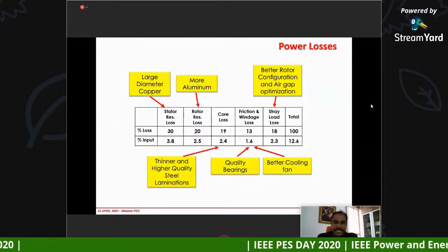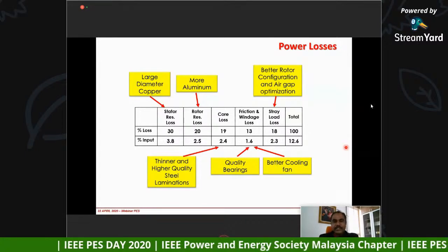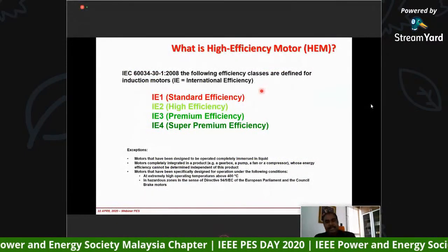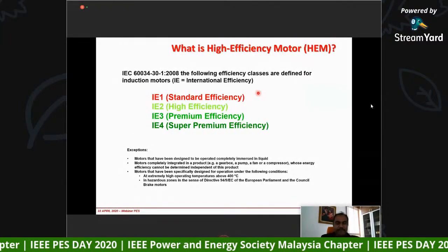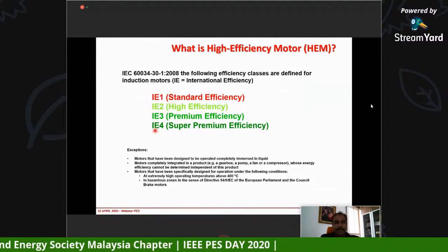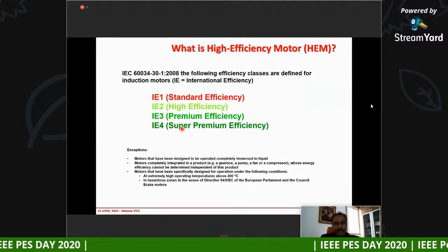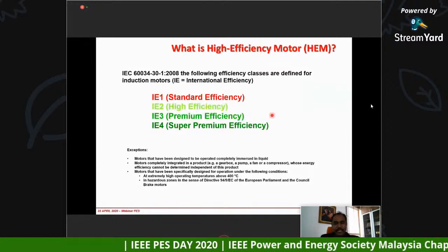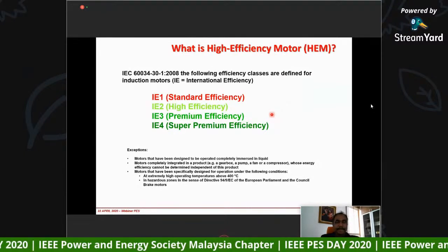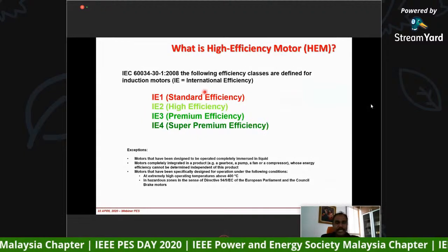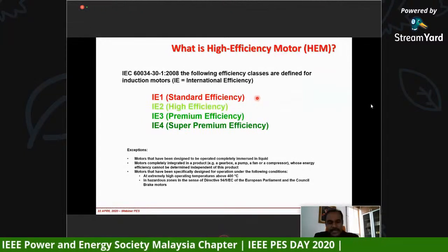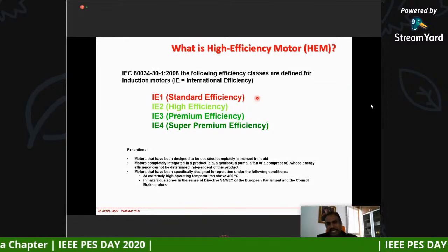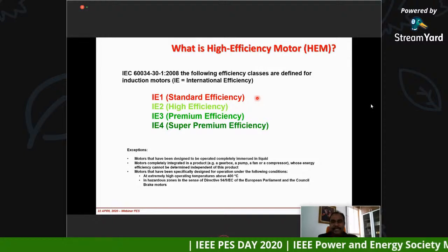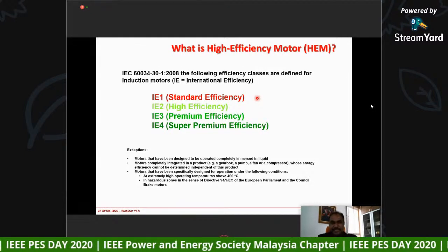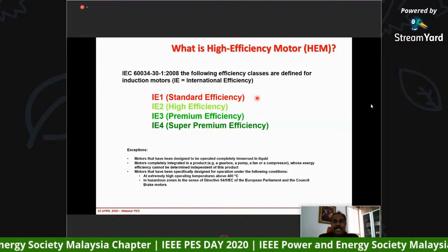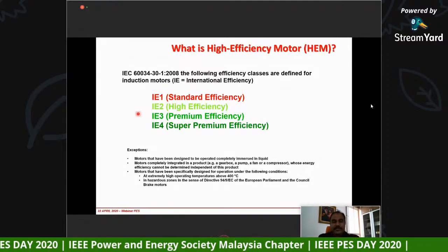So when they optimize this, then they categorize that motor into, at the moment, the ones that you are able to get from the shelf. They categorize it as 1, 2, 3, 4: IE1, IE2, IE3, IE4. This is under the IEC 60034-30-1, 2008. Now, what is this IE1 motor? The IE1 motor is the standard efficiency. That means, in other words, the motors that you have in industry now, we will put them under the category of standard efficiency. This is not a high efficiency motor, but a standard efficiency, IE1. Now, when you say high efficiency motor, it starts from IE2, IE3, IE4.